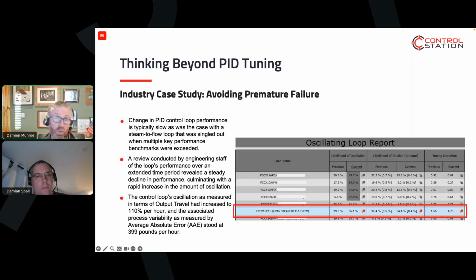How do you find a problem starting to happen? It could have been there for a long time, but if you have some method of reporting average absolute error increase, oscillation, frequency of oscillation increase, lack of control, something that shows you how, maybe the first time you hear about it is when you get a high level alarm. If you don't have monitoring systems to proactively look after your process from a PID point of view, the first thing you know about it, and it's normally the case, is when you hit that high level alarm due to oscillation increasing and forcing the system into higher average absolute error. We have tools with Plant ESP that will monitor that oscillation.